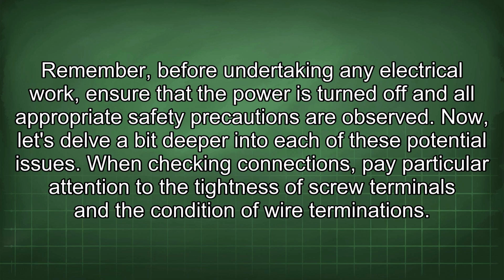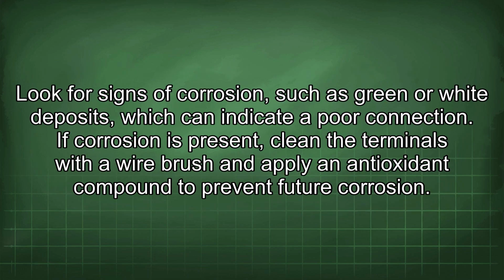When checking connections, pay particular attention to the tightness of screw terminals and the condition of wire terminations. Look for signs of corrosion, such as green or white deposits, which can indicate a poor connection. If corrosion is present, clean the terminals with a wire brush and apply an antioxidant compound to prevent future corrosion.